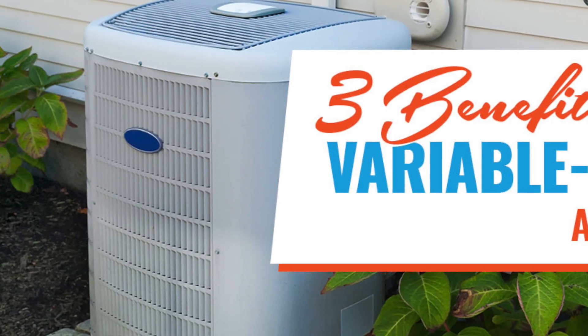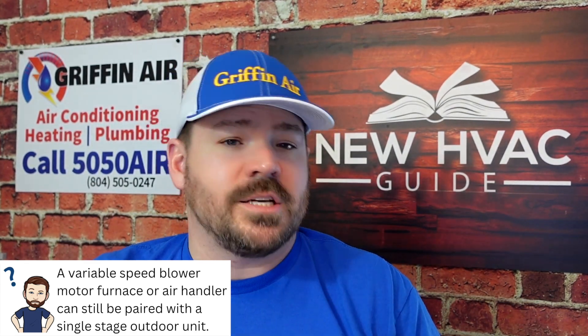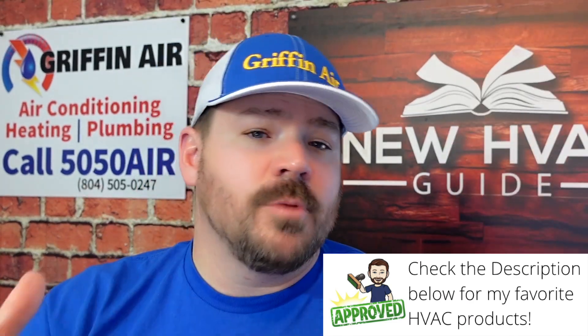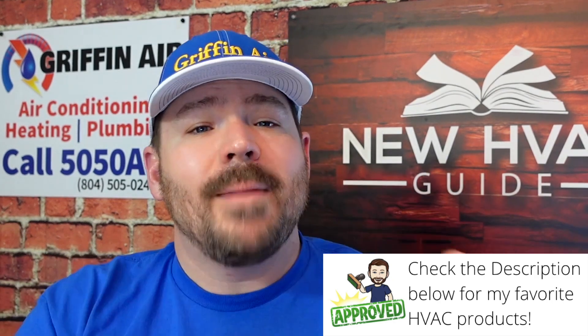In some cases it confuses folks. A lot of contractors will say variable speed system, but what they're really alluding to is the indoor fan motor is variable speed. It does not necessarily mean you have an inverter, VRF, or VRV type outdoor unit, or even a compressor that has variable or inverter capabilities. We've seen variable speed air handlers or furnaces matched with a single speed outdoor unit. Does it make it a little more energy efficient? Yeah, a little bit, but it's not the same thing. Just be aware that if somebody throws around terms like variable speed, they may not necessarily mean an inverter system, especially a communicating inverter system.